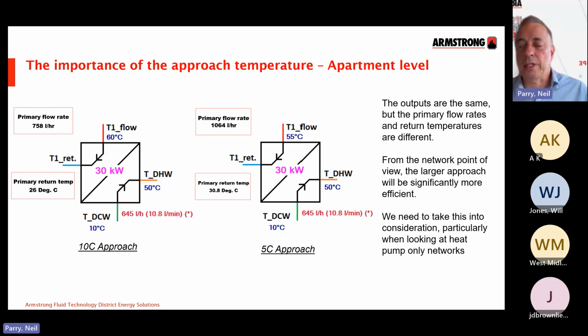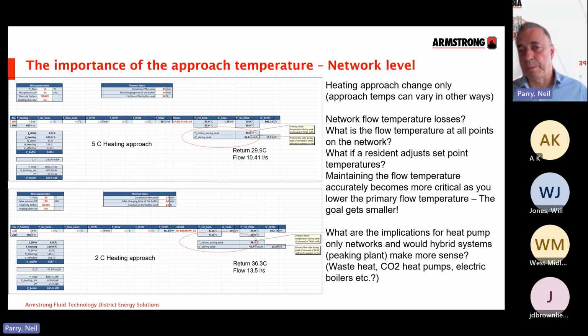When we start to look at the system as a whole, you can see here I've done a calculation, and all I've done is adjust the approach temperature of the heating circuit. And what we can see here, with a 5-degree approach, we have a 29, well, let's call it 30-degree return temperature with a flow rate of 10.4 litres per second. If we drop that down to 2 degrees, we can see that your return has gone up significantly to 36. So it's 6 degrees higher in return temperature, and you need another 3 litres per second on top just to deliver the same amount of energy. So you can see the benefits of holding a bigger approach temperature.